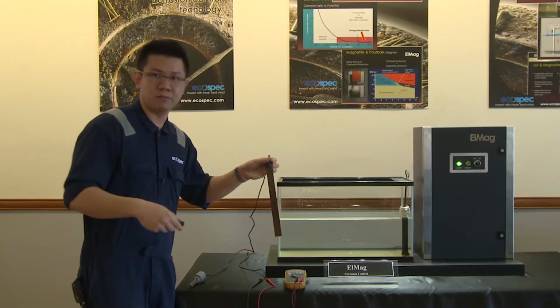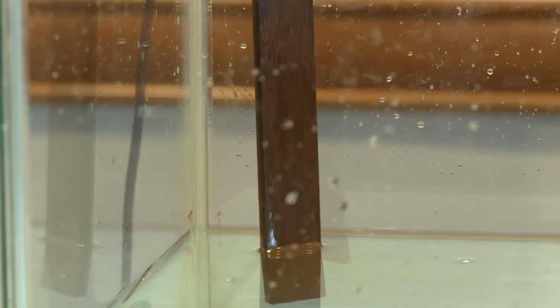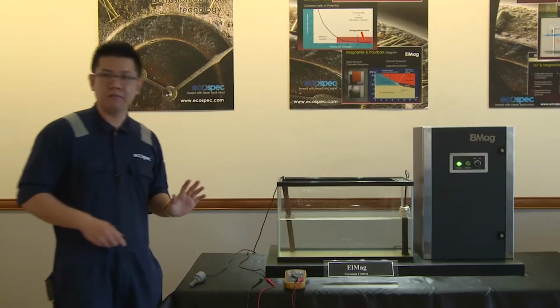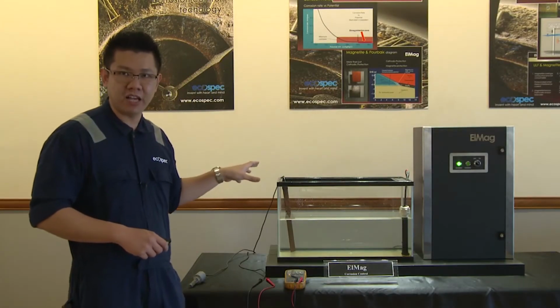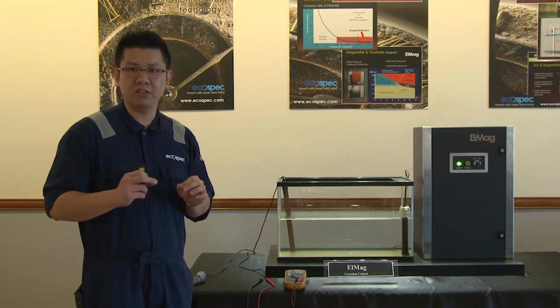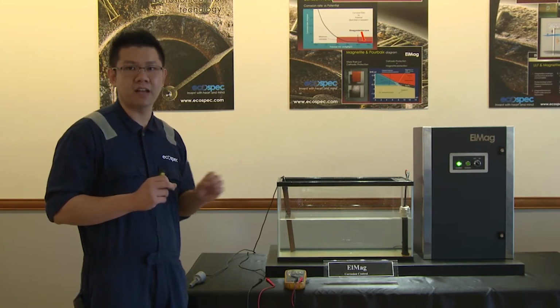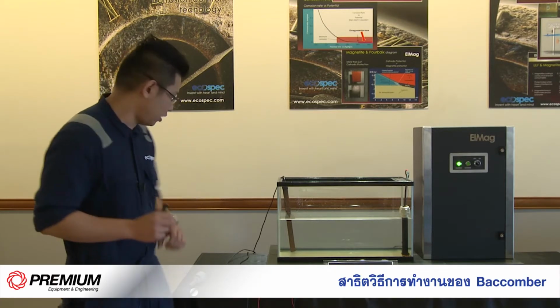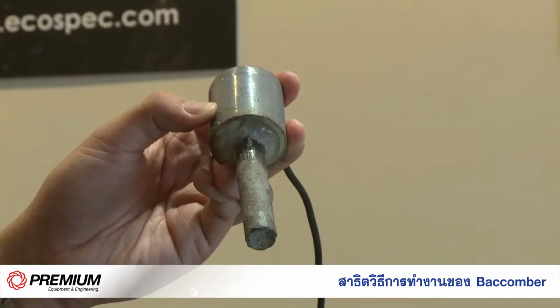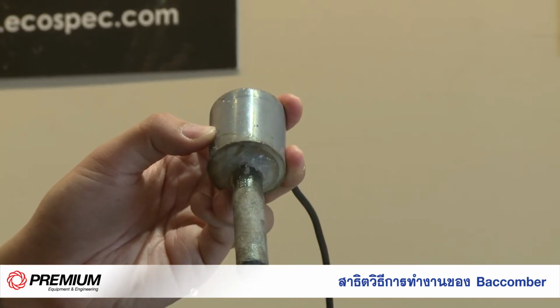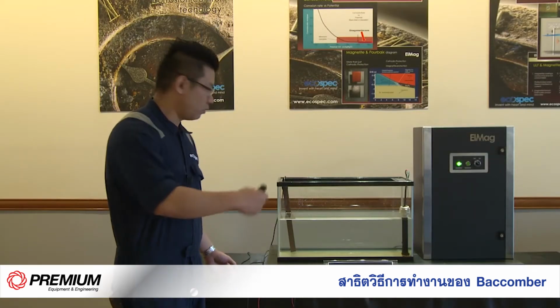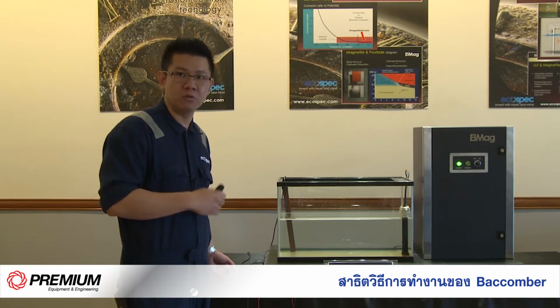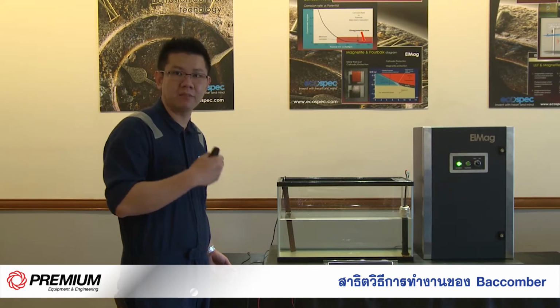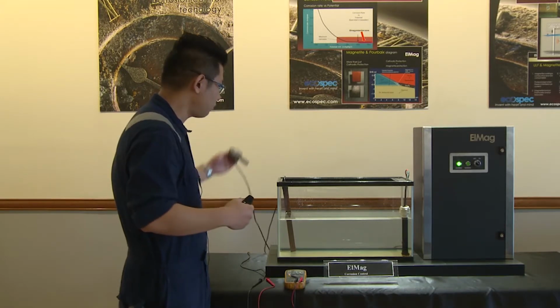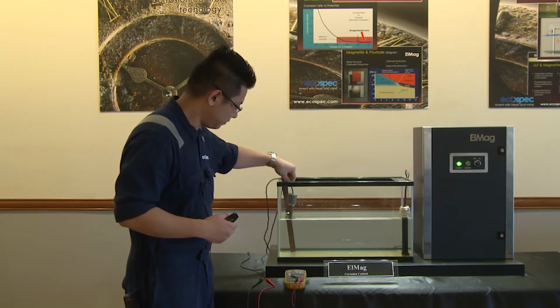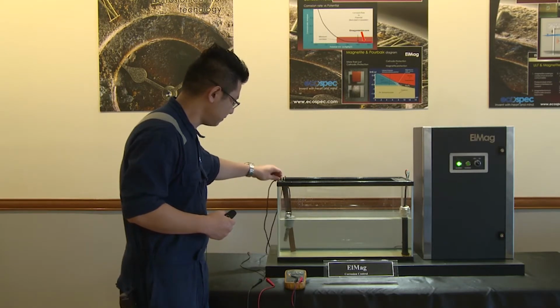Okay, so now this test piece, we lower it down into the water, right? So before we start, we could check the surface potentials of the test piece. And the surface potential values will tell us whether the test piece is protected or not protected, right? So we have a reference cell here. This is actually a zinc reference cell. So before we start, we can measure the surface potential of the test piece. So by now lowering down the reference cell, we are able to measure the potentials.